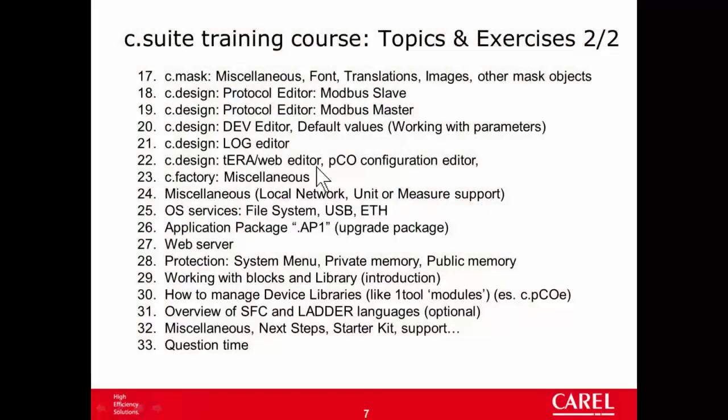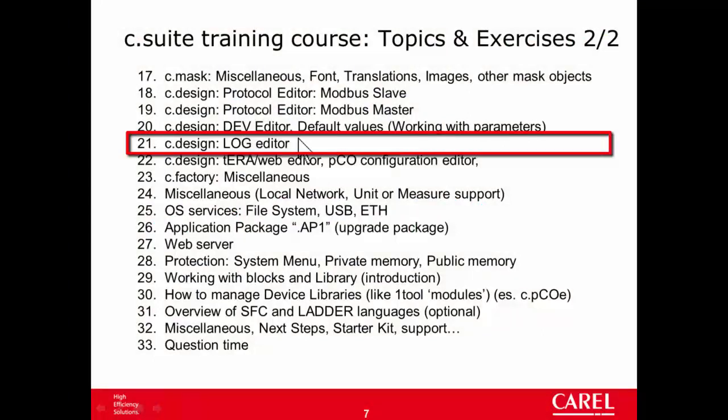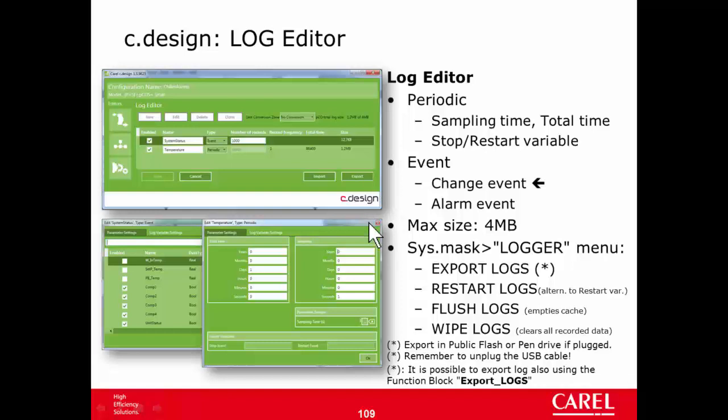The next editor in CDesign is the log editor. With this editor we can configure the built-in data logger. There are two types of logs: periodic, where the variable or variables are logged every given sample time, and event, where the variables are recorded according to a given trigger condition. The maximum size of the logs is 4 megabytes.